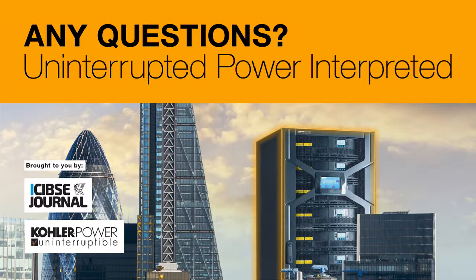Associated with the kit that is at the heart of the UPS, got a question here from Andrew, who asks, how critical is the replacement of capacitors in prolonging the life of a UPS? Yeah, very critical. Along with the batteries, capacitors and sometimes the fans are consumable items. The manufacturer will dictate when they should be changed. Failure to change those capacitors will mean that they could well fail in a quite catastrophic way sometimes. So you're putting the load at risk if you don't follow those manufacturer's instructions.